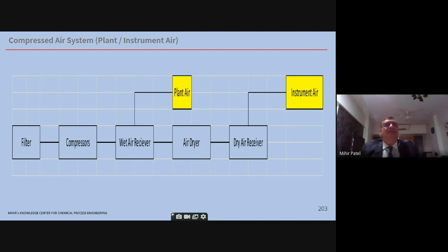The compressors are there. For small applications, you can go with a reciprocating type. Normally, oil-free screw types are recommended. Why oil-free? Because oil is not acceptable. It may choke the air dryer, as well as go with the instrument air and choke the actuators downstream. In a lot of places, however, oil-type compressors also are used. In that case, if the client prefers, fine, no problem.